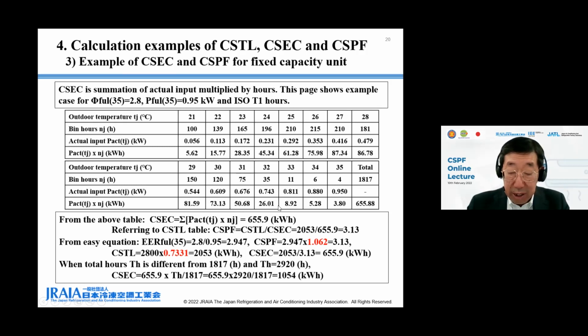Referring to the CSTL table in the previous page, cooling seasonal total load, CSTL, for this example is 2053 kilowatt hour. Cooling seasonal performance factor, CSPF, is CSTL 2053 kilowatt hour divided by CSEC 655.9 kilowatt hour, equal to 3.13. On the other hand, according to the easy equation in the previous page, CSPF is 35 degrees C full EER multiplied by 1.062.